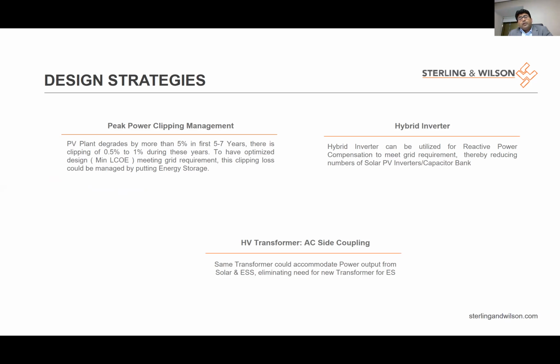But a lot of time we are not able to put a high amount of DC power solar panels because it results in clipping of power at the inverter level. Just to give you an example, if you load your system by 35 to 40% in a typical place like Dubai, your clipping loss could be as high as 1 to 2%, which is a lot of energy, especially when we're talking about big plants here.